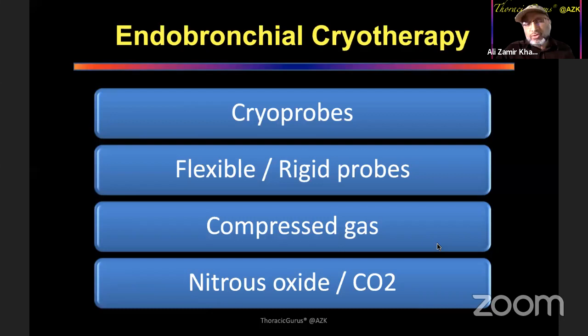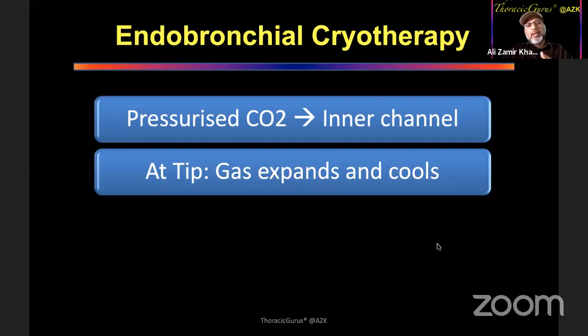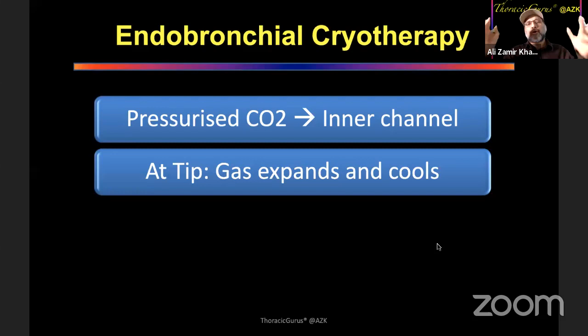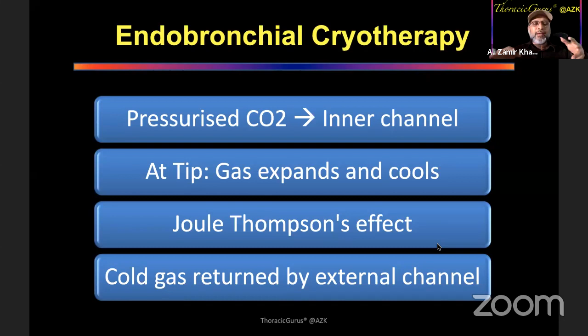And the gas is actually pressurized in the chambers, and there is an inner channel and there is an outer channel. So the pressurized gas is made to pass through the inner channel, and the moment it comes to the tip of the probe, it expands because the channel is narrow, and then when it goes outside, it expands, and any gas that expands cools. That is called the Joule-Thomson effect. Okay, so any gas under pressure, when it goes from one narrow channel to an open space and expands, it dramatically drops the temperature. And using that effect, you create an ice. And then the cold gas gets sucked back by an external channel. And I'll show you this in a minute. So this is how it is. Here is the internal channel, and the internal channel goes.